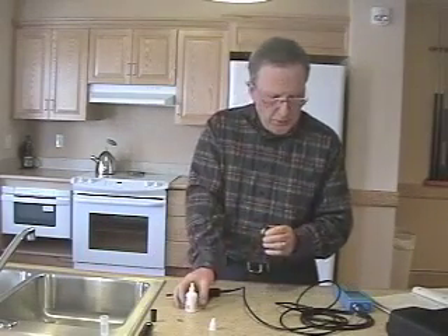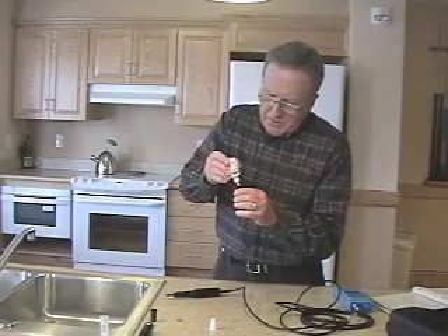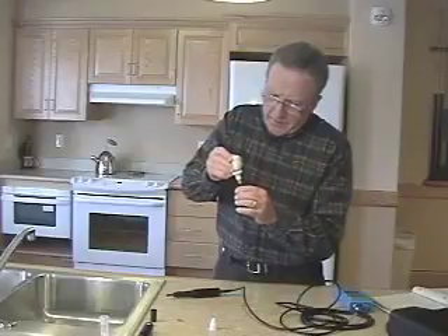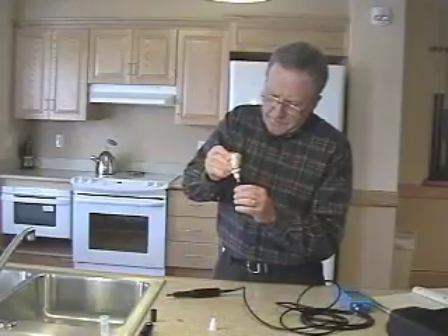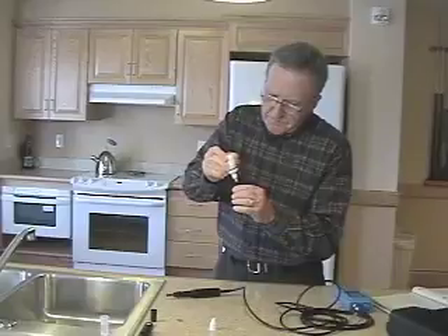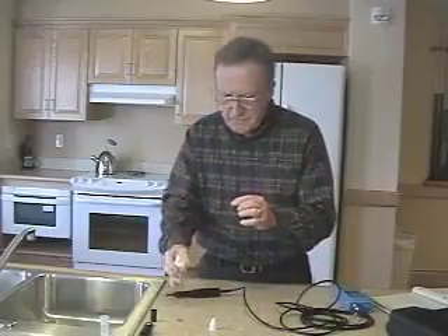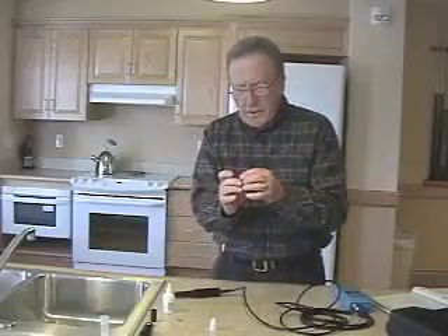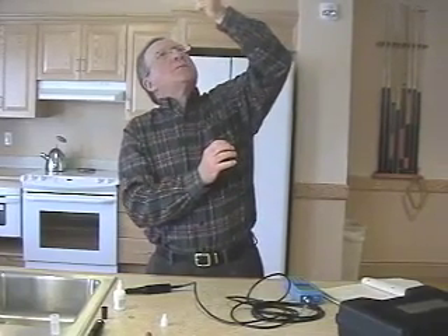Now I'm going to fill the membrane cap. You want to ensure there are no air bubbles on the membrane. So after you add the electrolyte, you gently tap the sides of the membrane cap. You can check for air bubbles. It looks good.